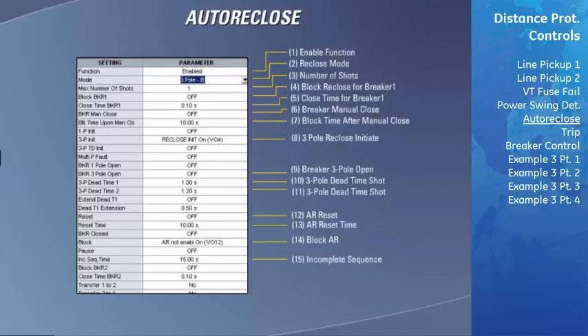Select a flex logic signal or input that will block the recloser for breaker 1. None was selected here. Set the maximum expected closing time of breaker 1. Here, 100 milliseconds was selected. Select a flex logic signal or input that will manually close breaker 1. Here, none is selected. A manual close will block the recloser. This time defines how long the recloser will be blocked for. Here it is set to 10 seconds.